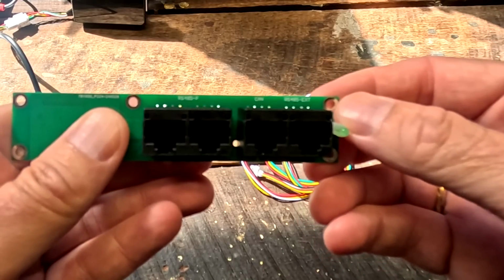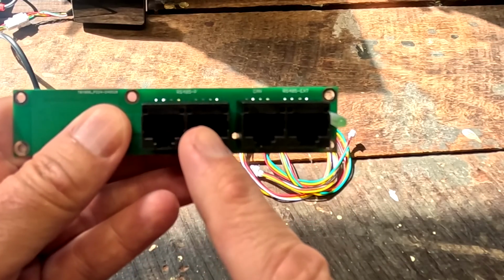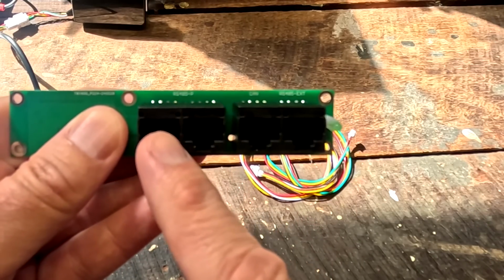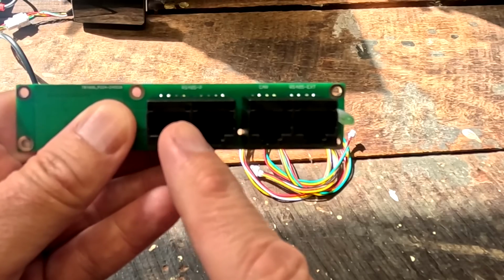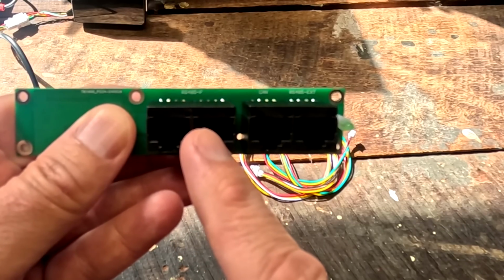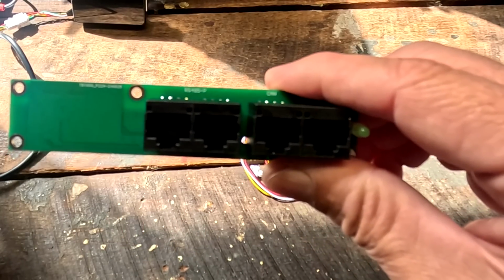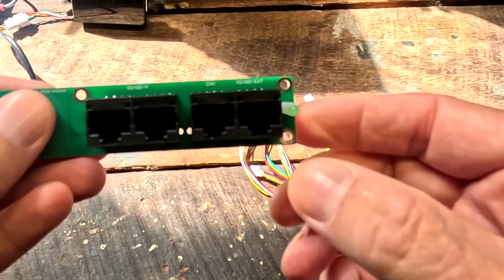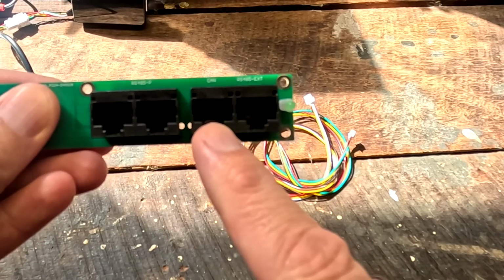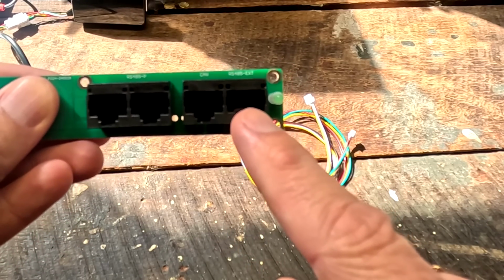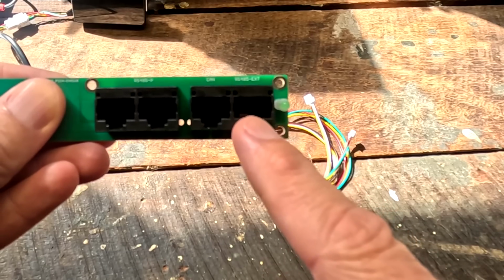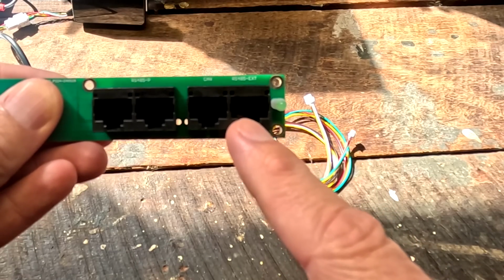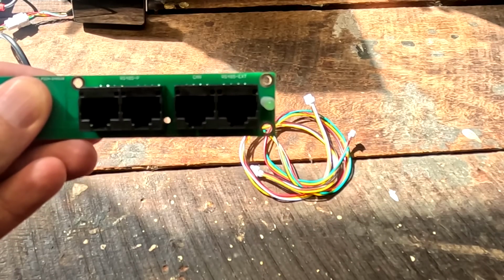That means we have communication here between the BMSs, like in the inverter style BMS as well, with internal RS485 ports to parallel multiple of these BMSs. We have external CAN communication to your inverter, and we also have external RS485 communication to your inverter if it only speaks RS485.